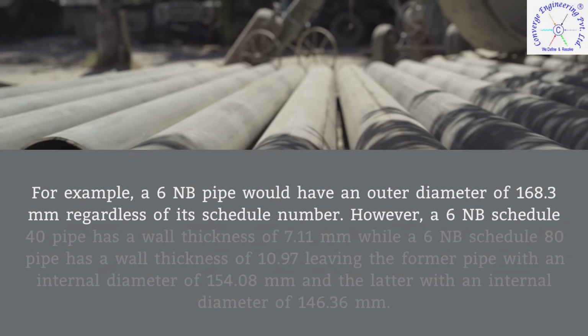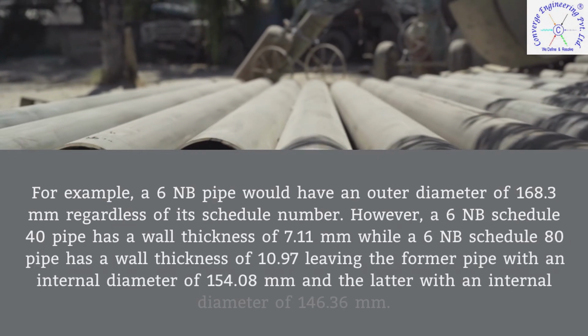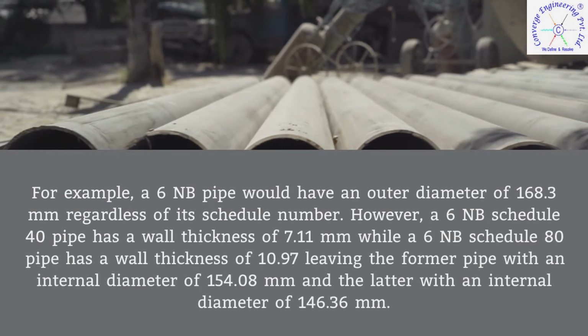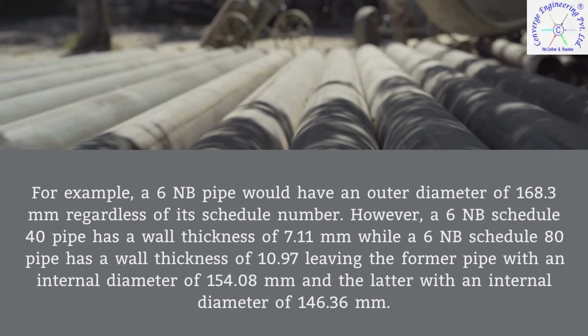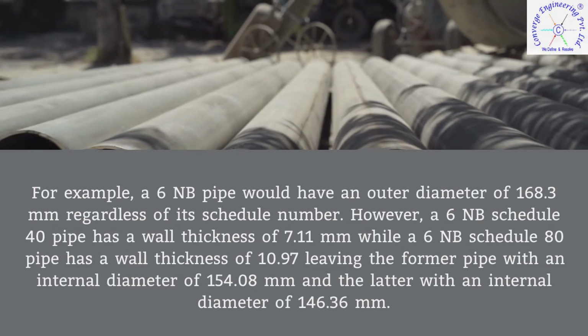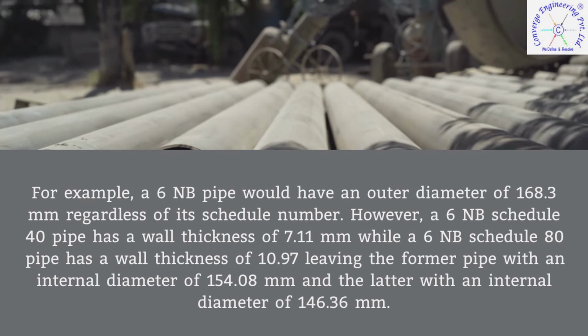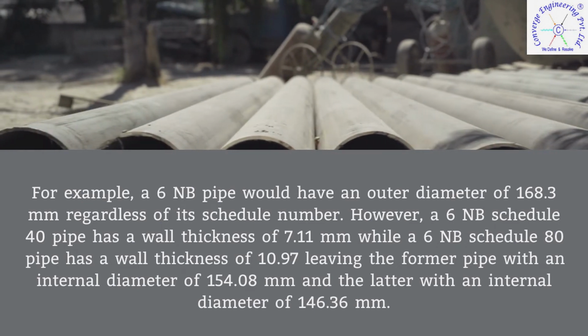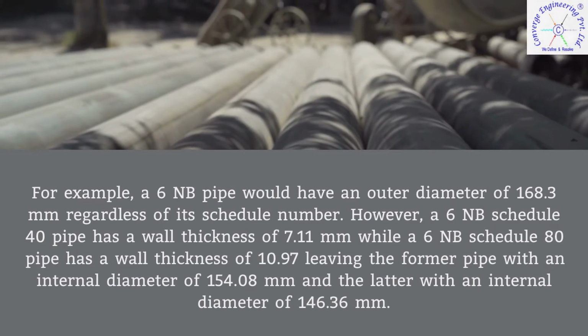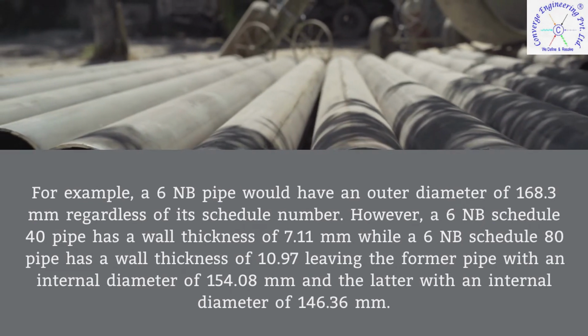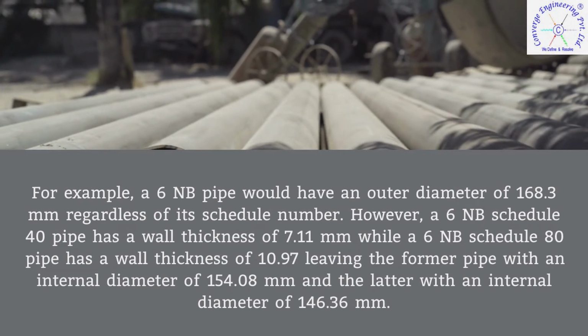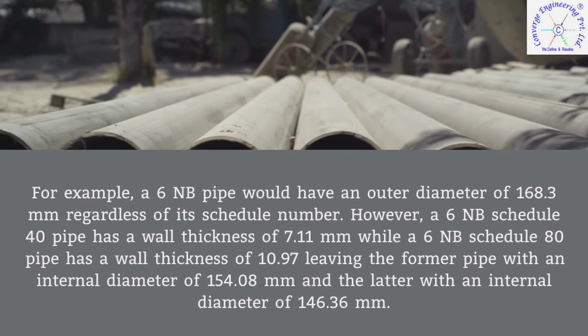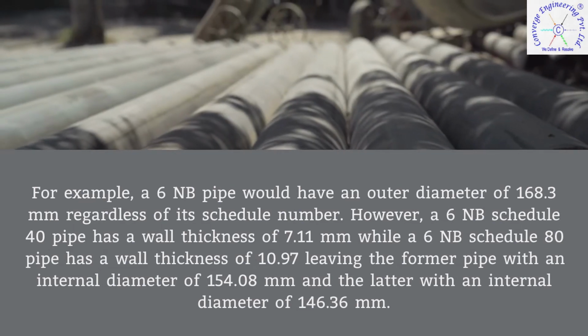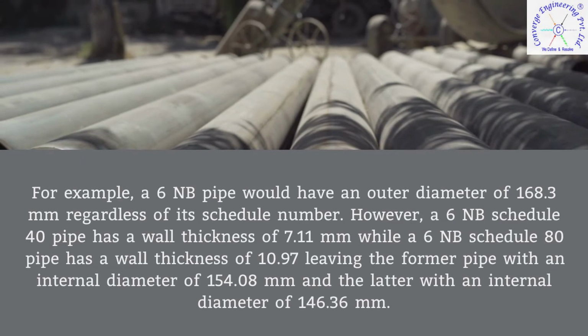For example, a 6 NB pipe would have an outer diameter of 168.3 mm regardless of its schedule number. However, a 6 NB Schedule 40 pipe has a wall thickness of 7.11 mm while a 6 NB Schedule 80 pipe has a wall thickness of 10.97 mm, leaving the former pipe with an internal diameter of 154.08 mm and the latter with an internal diameter of 146.36 mm.